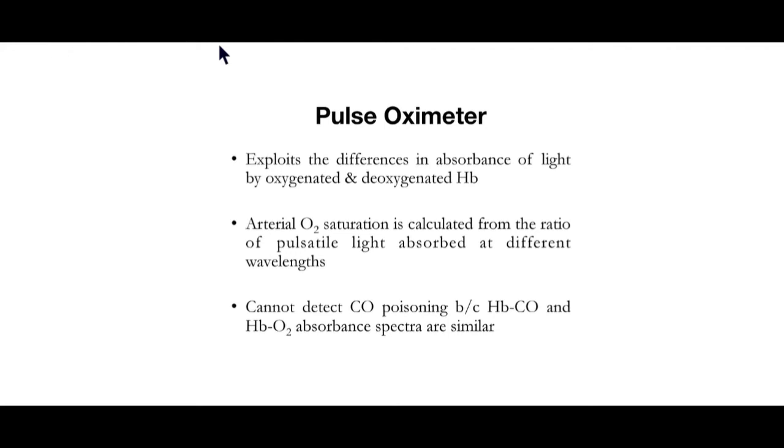Okay, so the saturation is calculated specifically by looking at the total amount of absorbance minus your non-pulsatile absorbance, right? Because you look at the total amount, get rid of the amount that's from your venous side, and you can figure out what the pulsatile or arterial saturation is.